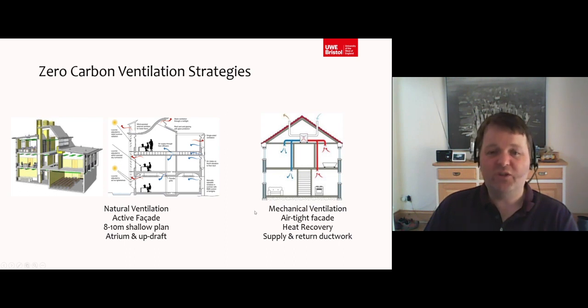A lot of buildings where they're not zero carbon buildings, they're quite leaky buildings, typically do work in mixed mode operation. They have a mechanical system and at 6 o'clock in the evening, enough people have gone home maybe and it turns off and they're still okay with just localized air ventilation. But when we talk about high performance zero carbon buildings, it's harder to justify the economic cost of doing both high level nat vent and high level sealed box system.